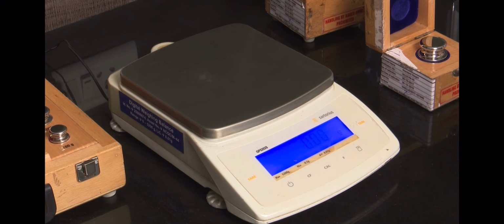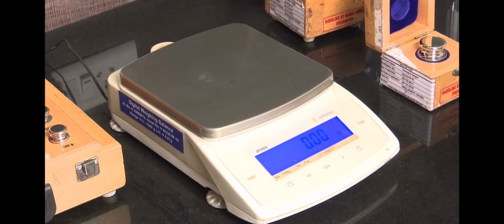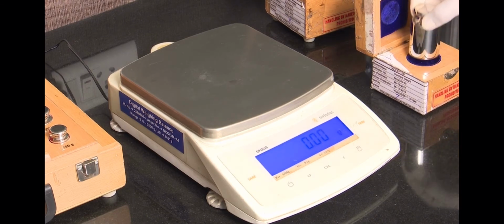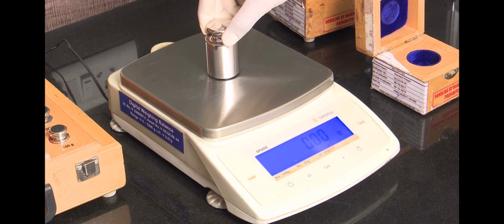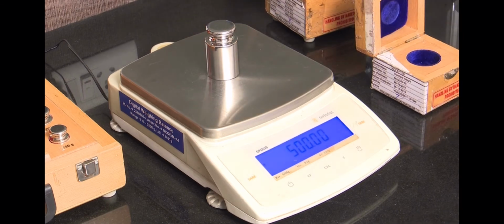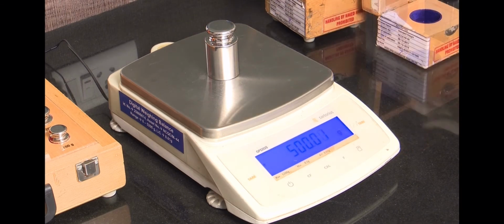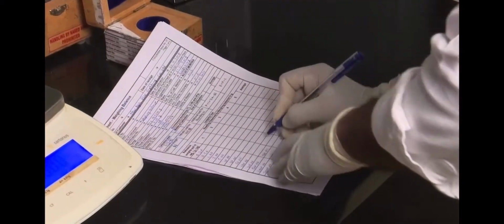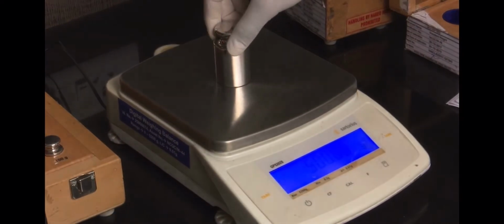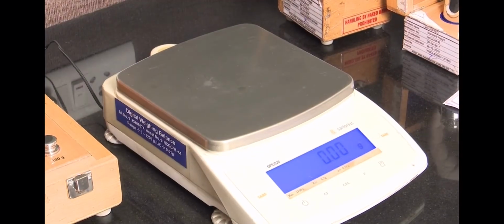Now I am performing linearity test. In this test, we should perform calibration at minimum 10 calibration points covering the whole range. Here I am demonstrating calibration at 500 grams. I am putting 500 gram reference weight on the center of the pan of balance. Now wait for stabilizing. In the worksheet, note down the reading shown by the balance against the reference standard weight. In the same way, we can take the readings for all other points as per given method.